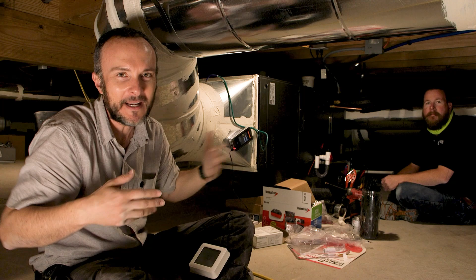Does testing of the sort we've done so far—static pressure testing and things like that—happen on a typical job? Not really, it doesn't happen very often. It has to be specific applications and things like that. It should be done on every install, every startup, but unfortunately it doesn't happen that often.